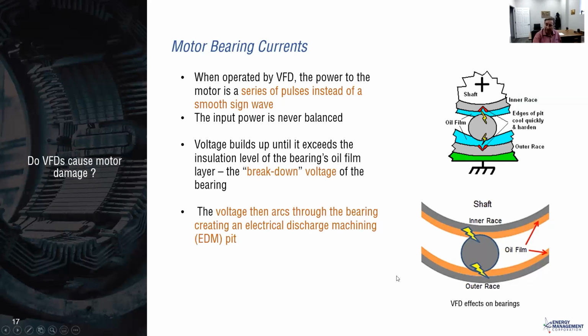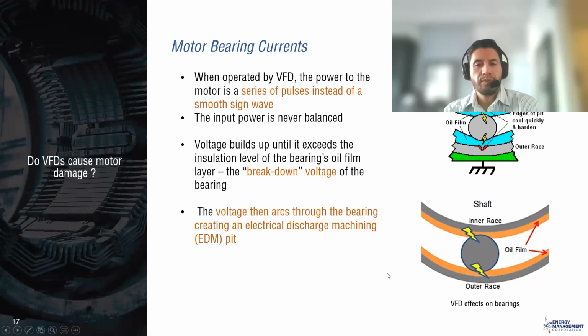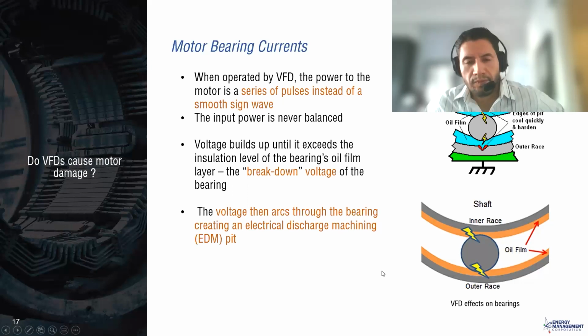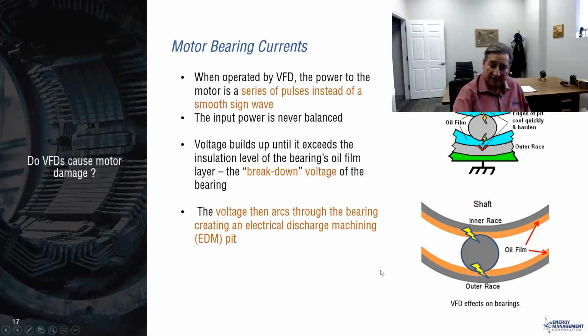Moving on to the bearing currents. That's the same waveform traveling in that conductor, but with the capacitive coupling, there's no symmetry between the ground and the individual conductors. So what you'll find is that this bearing is traveling on a film of oil, and the only insulation between that is that film of oil. And I think I need to move a little faster here.